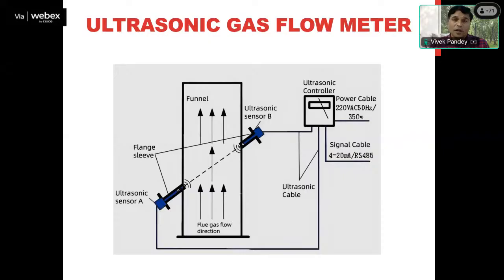In terms of mass or volume. If you look at this picture, you can easily understand. Suppose at a time ultrasonic sensor A is acting as a transmitter. It transmits an ultrasonic sound wave which reaches ultrasonic sensor B, which at the same time is acting as a receiver. It will reach in a lesser time. Why? Because the gas is flowing in the upside direction, which supports the movement of the sound wave. So it takes less time to reach from A to B, and the moment it reaches B, the information is collected by sensor B and supplied to the ultrasonic controller.